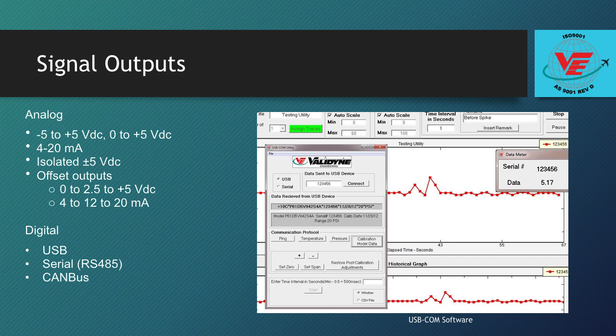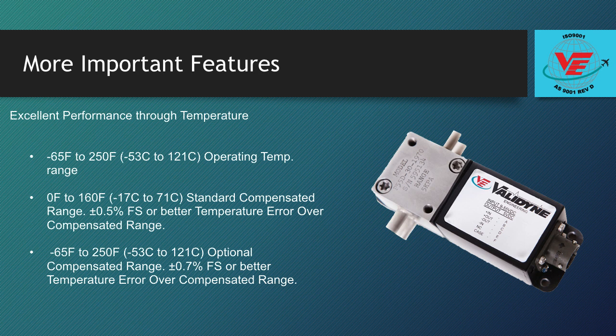Finally, there are new variants of the P55 with digital output capability, USB, CAN bus, and serial outputs option where pressure, temperature, calibration data, as well as the ability to set zero and span can all be done digitally. The P55 can operate at temperatures from negative 65 degrees Fahrenheit to 250 degrees Fahrenheit. We offer two options for temperature compensation. The standard is 0 degrees Fahrenheit to 160 degrees Fahrenheit, as an optional wide range of negative 65 degrees Fahrenheit to 250 degrees Fahrenheit. The result is that the total error, including temperature effects and sensor error, is just 0.5% FS for the standard operating range.